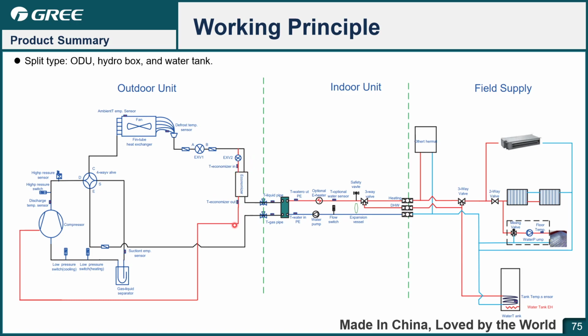This pipe is the EVI pipe. Because of the economizer, if this expansion valve is open, the unit will distribute some refrigerant to the economizer, evaporate it, and then inject it to the compressor. Especially in winter or very cold ambient, it uses this technology to reduce the exhaust temperature and keep the unit running stable.